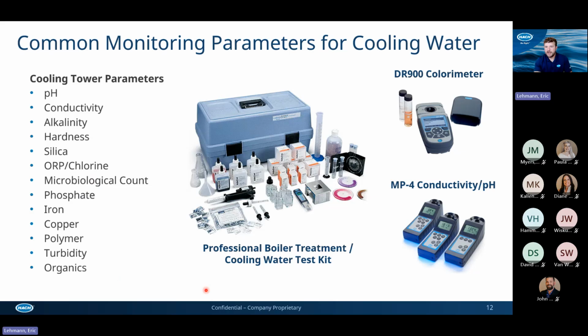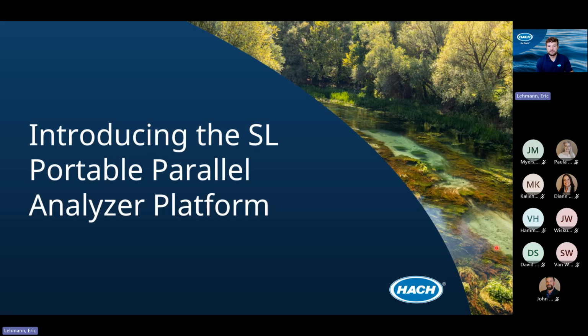So there's a number of ways to run these tests. You might have a professional boiler treatment kit, something like this, big blue box with all the reagents, chemicals, titrators in it. A lot of our water treaters use what's called a DR900 colorimeter. So we have the little powder pillows, and they have a colorimeter running the test independently. Or you might have the MP4 conductivity pH meter. You pour the sample right into this little well for pH and conductivity. So there's a number of different ways to run these tests.